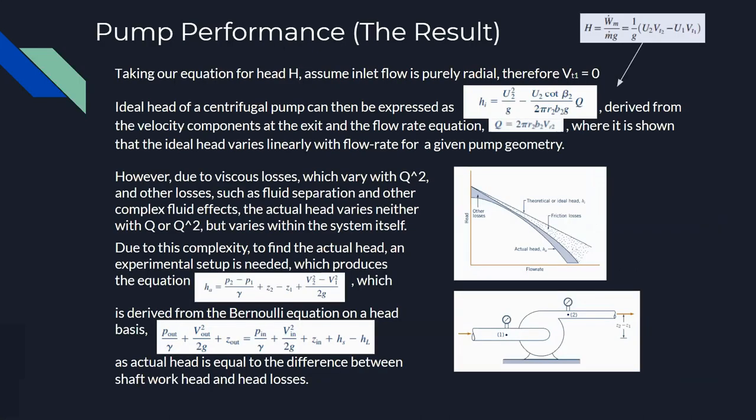To find pump performance, we must first find the ideal head of the pump, which shows a linear relationship with flow rate for ideal head. This is because as flow rate increases, tangential velocity decreases, reducing the work done on the fluid and thereby decreasing head rise. However, actual head differs from ideal head due to head losses.